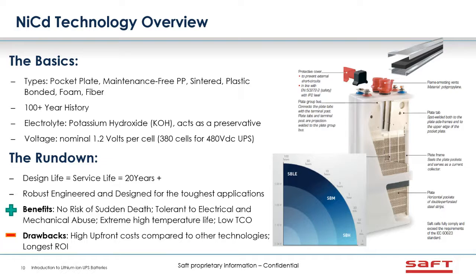It acts as a preservative, and it's just there to transfer the ions inside the batteries. It's not part of the chemical equation to get energy out like the lead acid battery. So it's really there as a preservative. Voltage for these batteries, 1.2 volts per cell. So we actually need 380 cells to build up a voltage of 480 volts for a UPS. So a lot more cells are required for this particular technology.